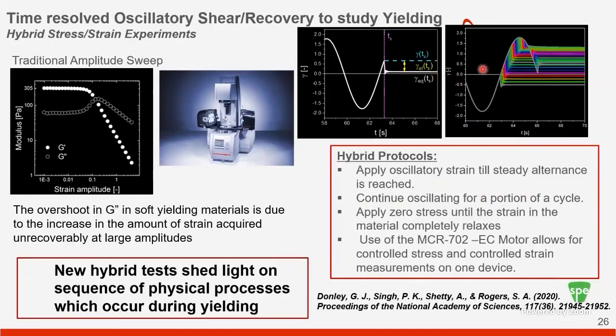And this is a very unique experiment, where in a typical oscillation cycle you're stopping at different instances in the cycle and creeping to zero stress. So you need a device which can actually switch from strain to stress control seamlessly. And here again, the multi-drive device with the EC motor, the electronically commutated motor, really does a great job because it allows for controlled stress and controlled strain type measurements on one device. And these new hybrid tests really shed light on the sequence of physical processes which actually happen during yielding.